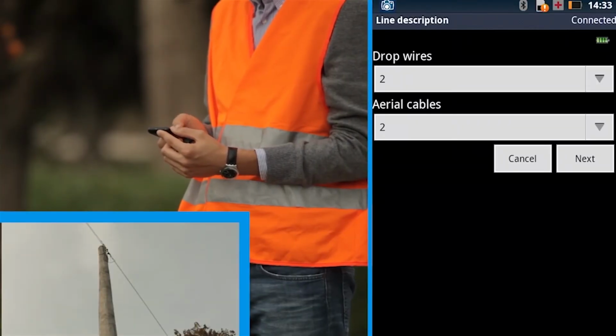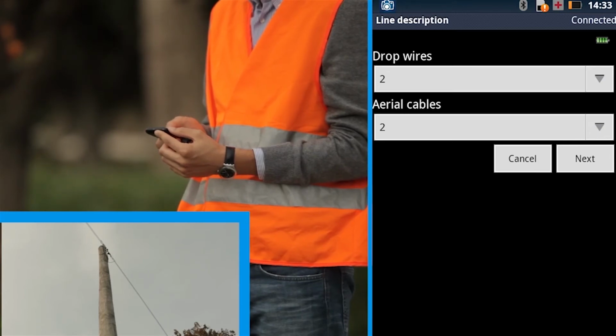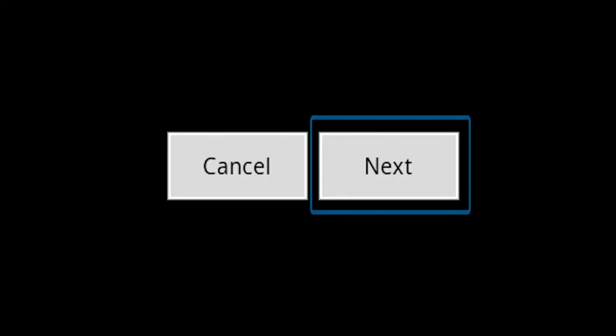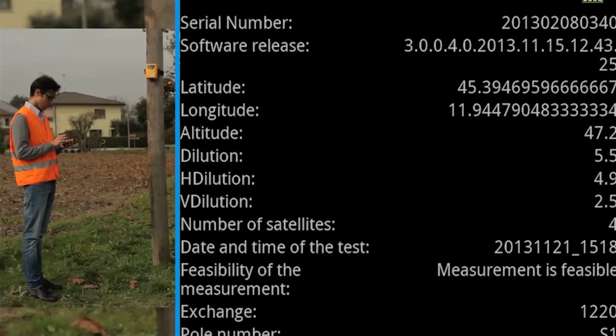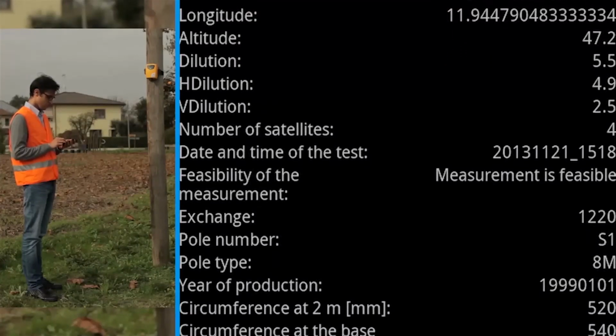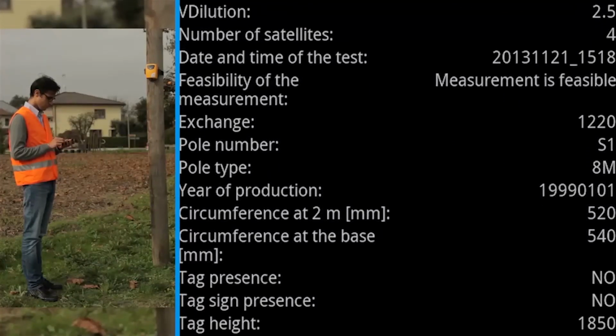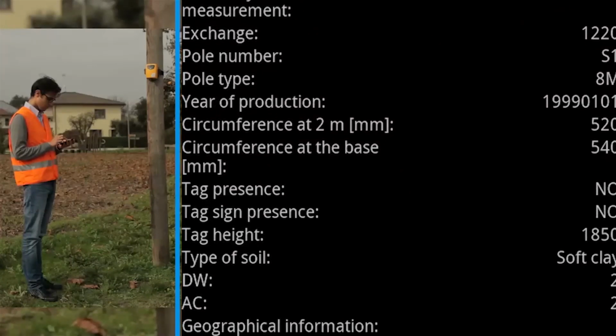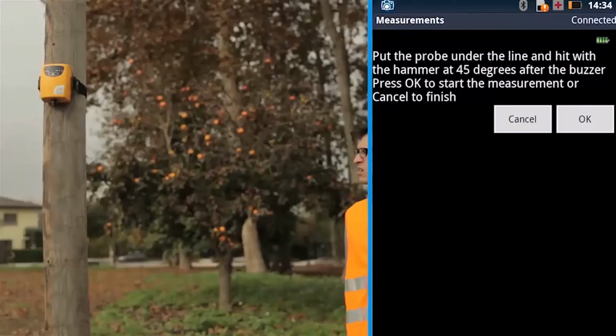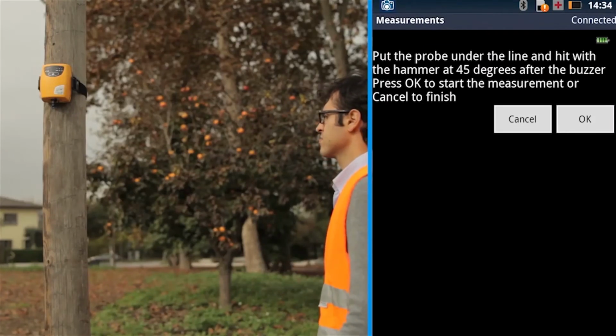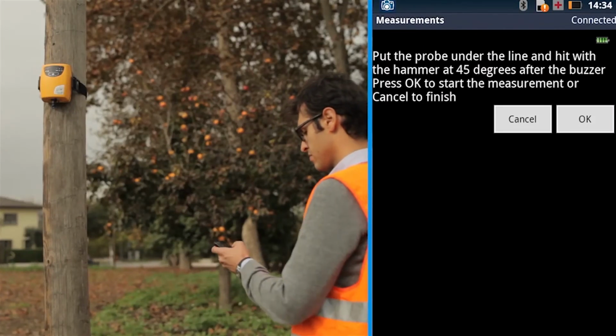Input the total number of drop wires and the total number of aerial cables. Press Next. All the information needed for the measurement is now entered into the device. Check the summary page and press Next to continue with the measurement. The second phase of the measurement will start. It consists of the measurement of pole frequencies.